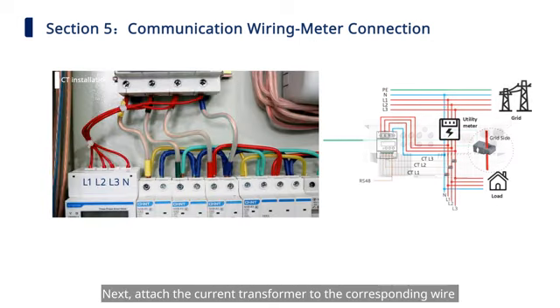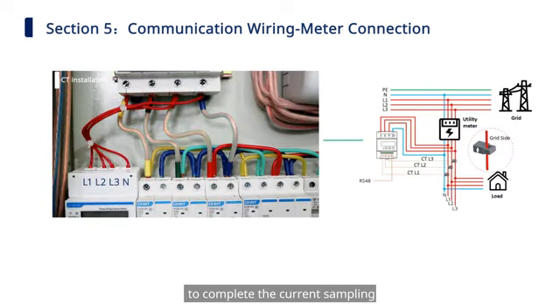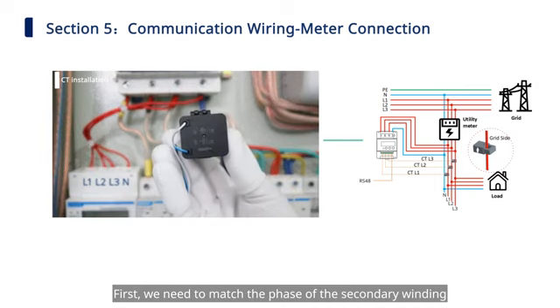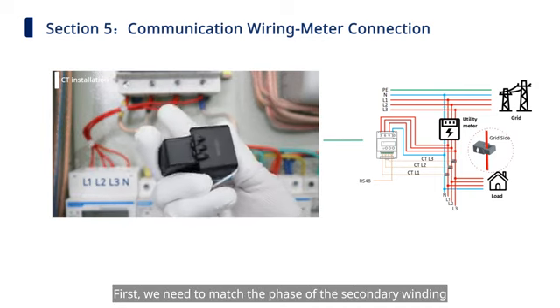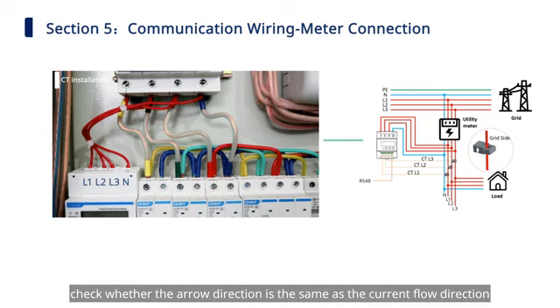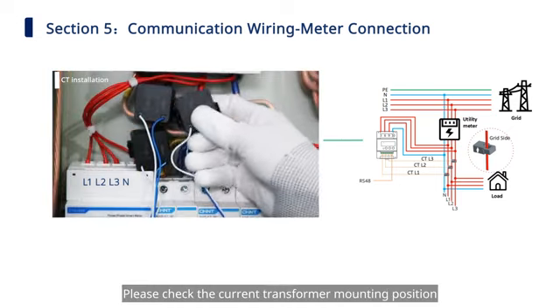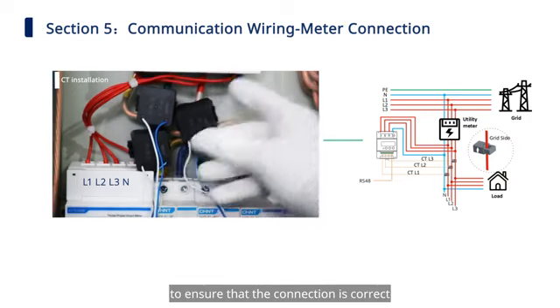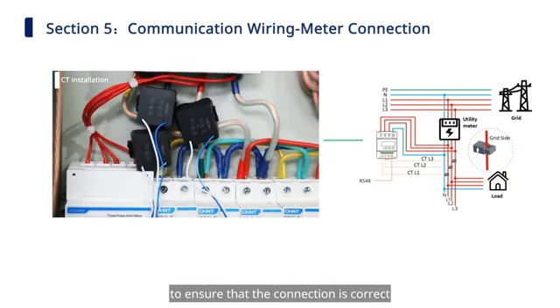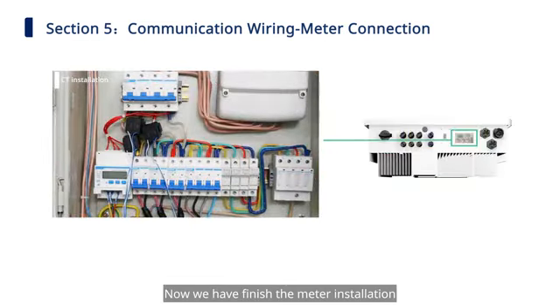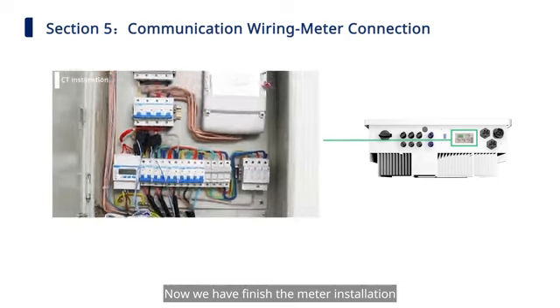Next, attach the current transformer to the corresponding wire to complete the current sampling. First, we need to match the phase of the secondary winding with that of the distribution box, and then, check whether the arrow direction is the same as the current flow direction. Please check the current transformer mounting position to ensure that the connection is correct. Now, we have finished the meter installation.